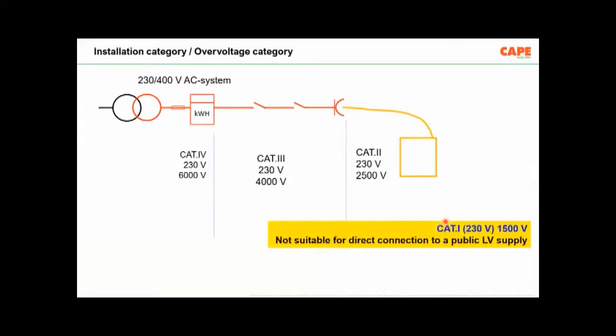When we select electrical appliances in your electricity distribution in your building, at the point of commencement of supply, all the electrical apparatuses must be of category 4. That means a 230 volt item must withstand a 6 kV voltage impulse. The connected equipment must be of category 2, 2500 volt. These are the minimum voltage potential differences or voltage impulses the equipment are supposed to have.